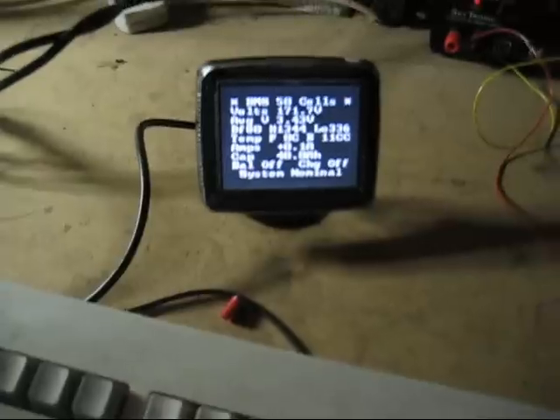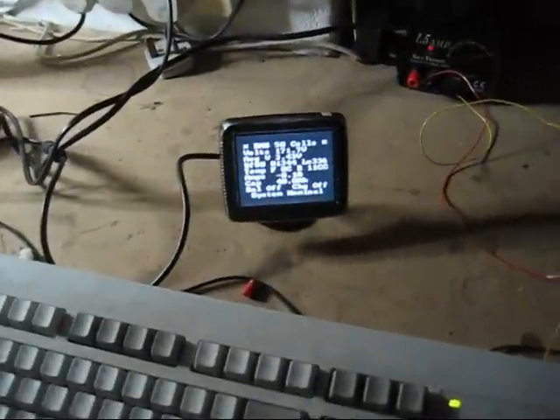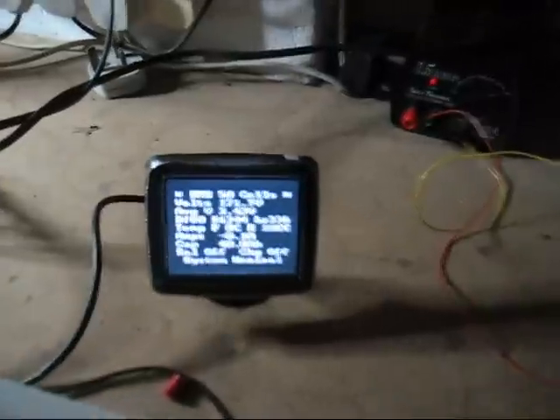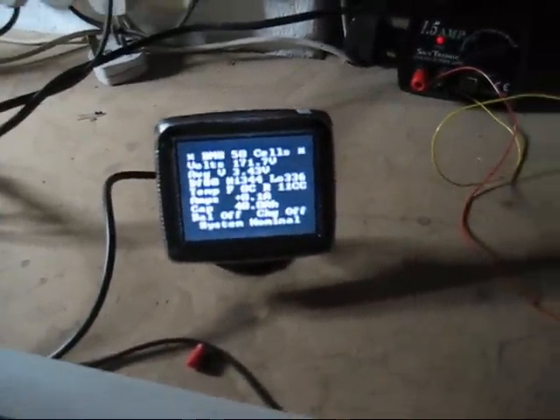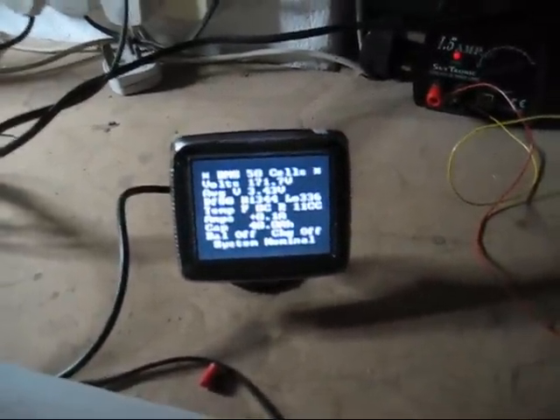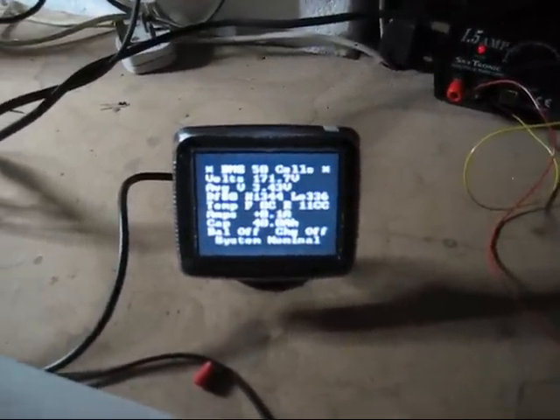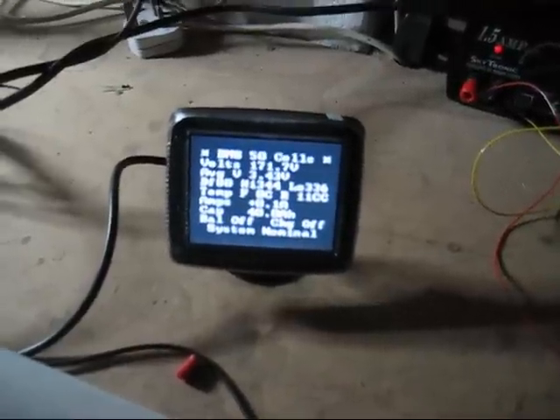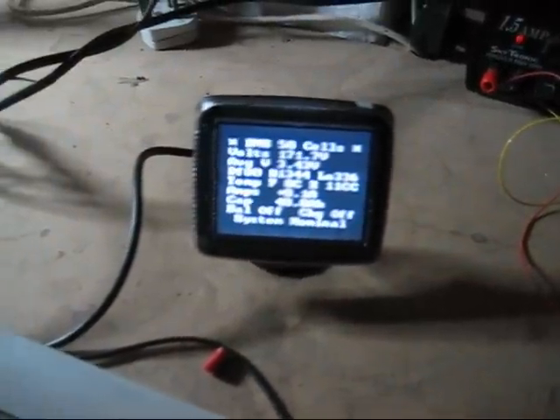Now if the charger had been operating when the error occurred, it would have immediately tripped off the charger. The charger can only be reset by resetting the master board or reinitialising the charging sequence. The charging sequence won't restart after an error without the user's intervention.